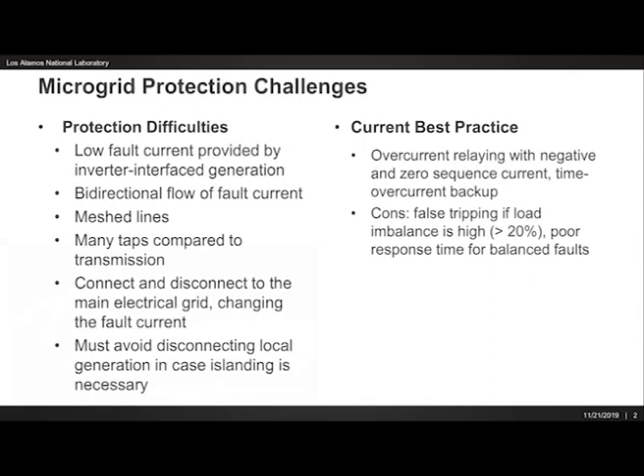So the first thing I'd like to go over with everyone is, why is microgrid protection difficult? There are a number of reasons for this. When we typically think of microgrids, we think of them being supplied by inverter interface generation, be it spark ignition engines, microturbines, PV. Also, microgrids will operate in both islanded and grid-connected mode, so we can get very different fault currents in different operating regimes. In addition, we may have microgrids that have a mesh structure as opposed to a radial structure. So all of these are difficult for traditional distribution system protection.